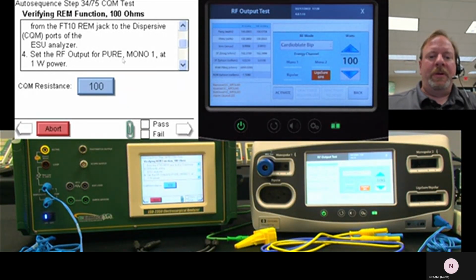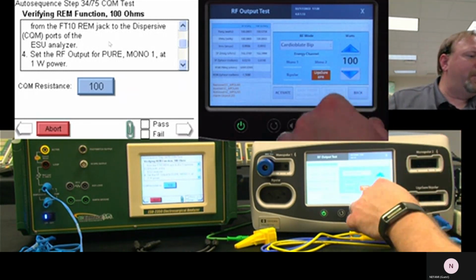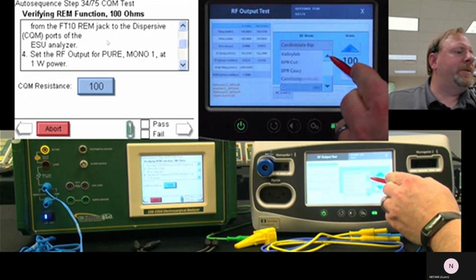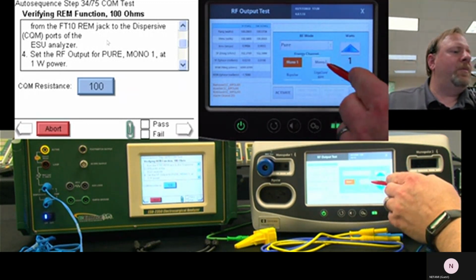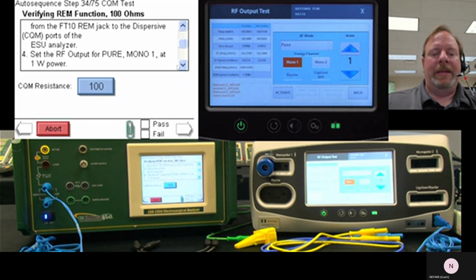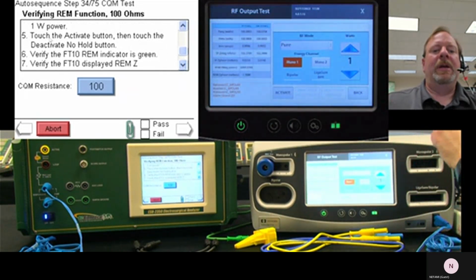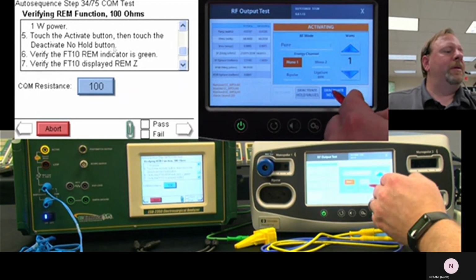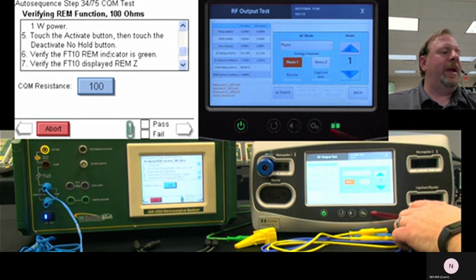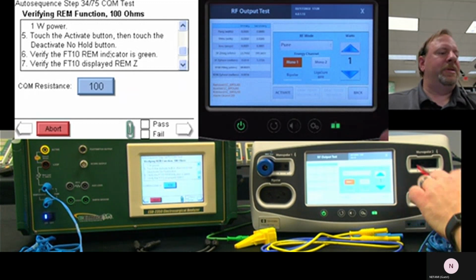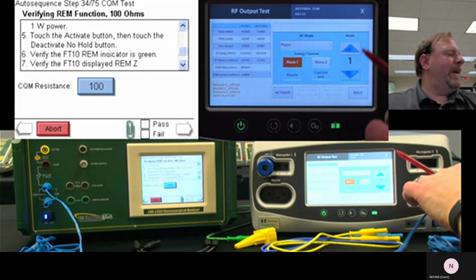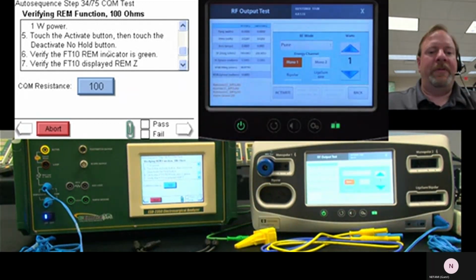Set RF output for pure mono 1 at 1 watt power. So follow our instructions. Pure mono 1 watt. Now it doesn't tell me to connect anything to the active. Touch the activate, then touch the deactivate, no hold. Okay, so activate, deactivate, no hold. Now what we'll see is that the indicator went green because we're not worried about the pin. We're just testing the resistance measurement function. And the 2350 is set to 100 ohms. Now I can't go in here and change this again, because this is an auto sequence, this is locked. So I can't change the setting, but at least it's telling me what it is.